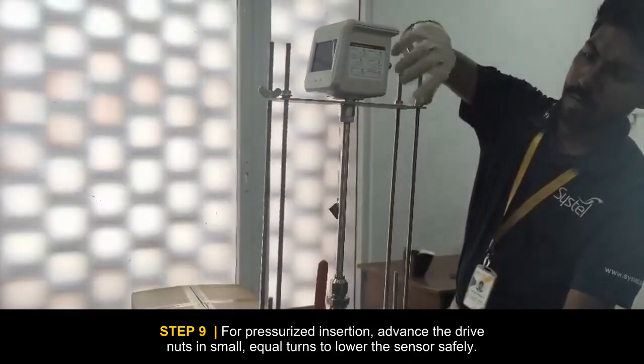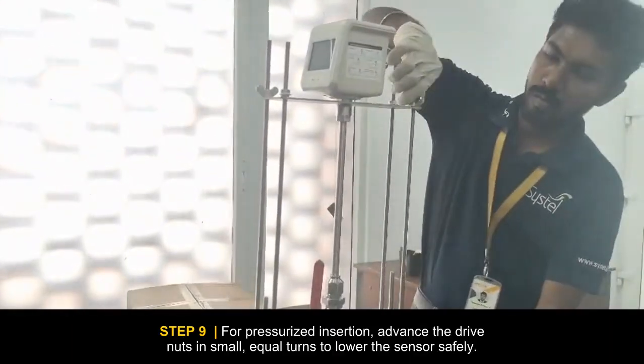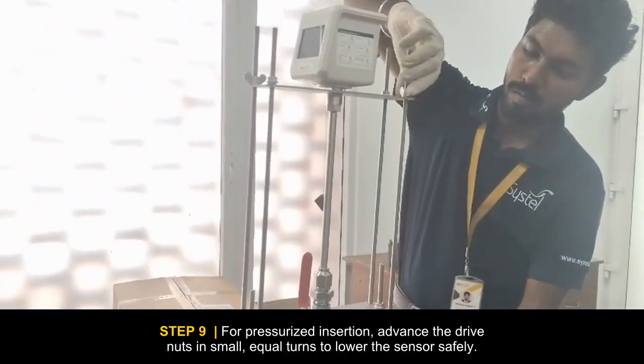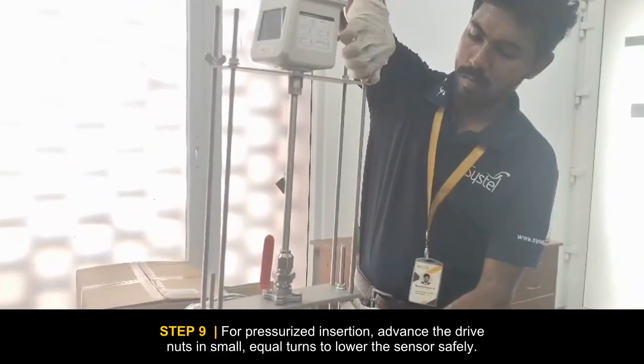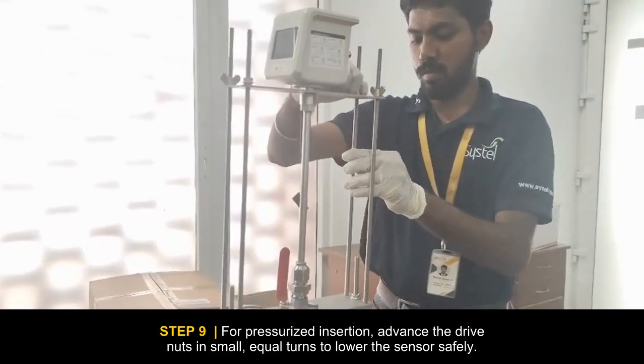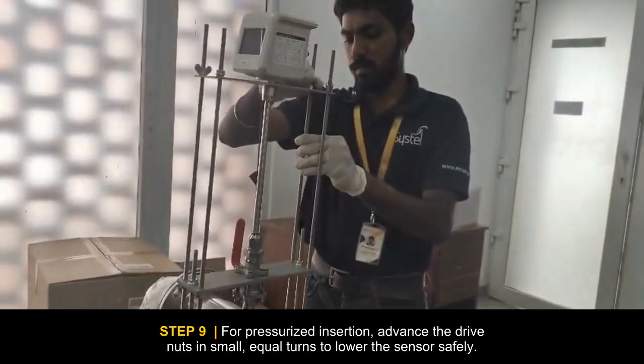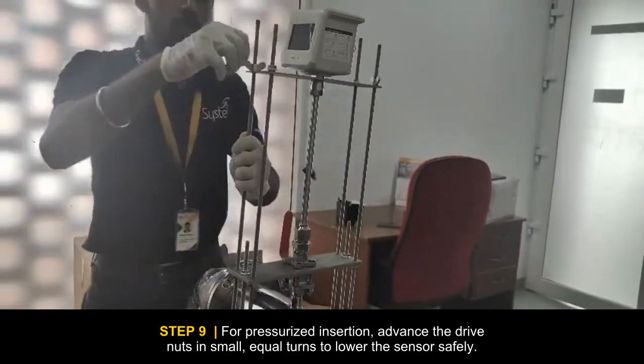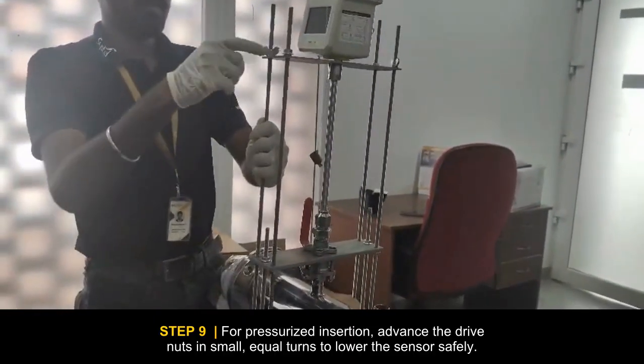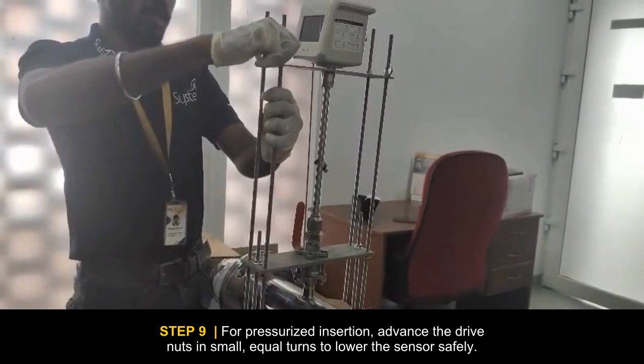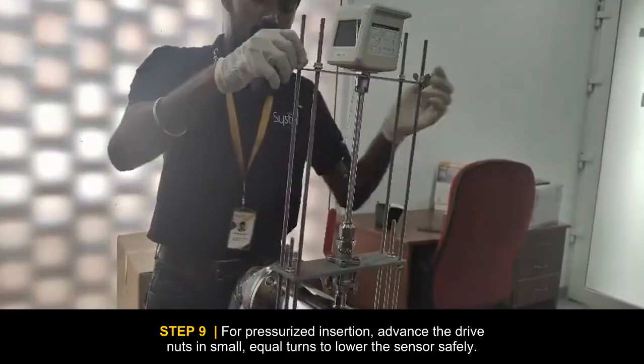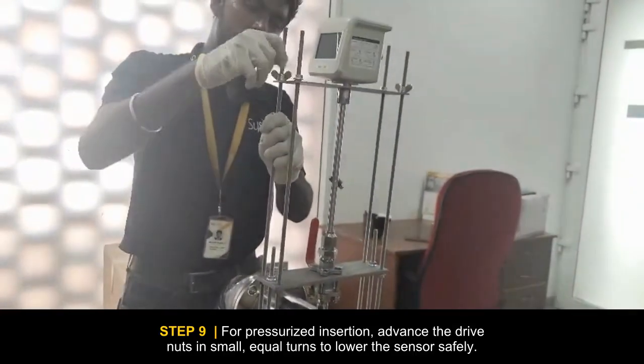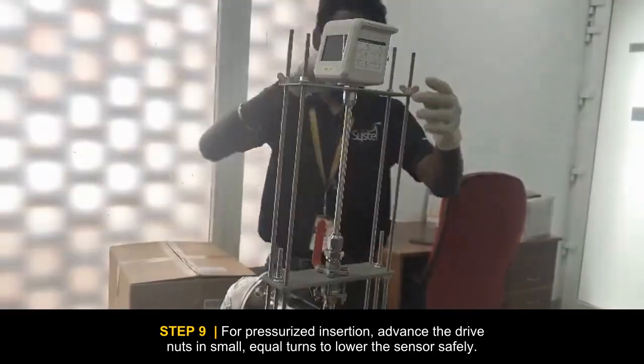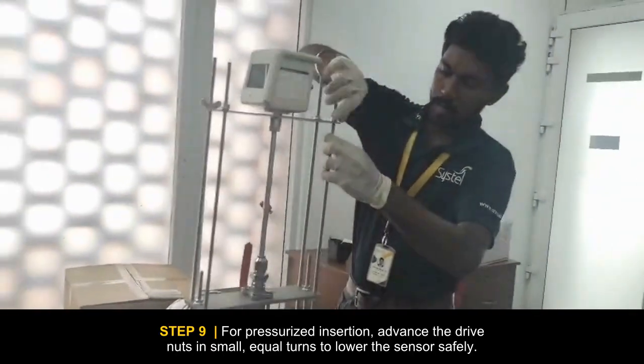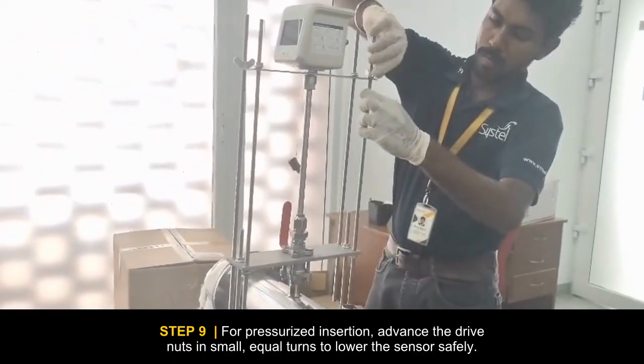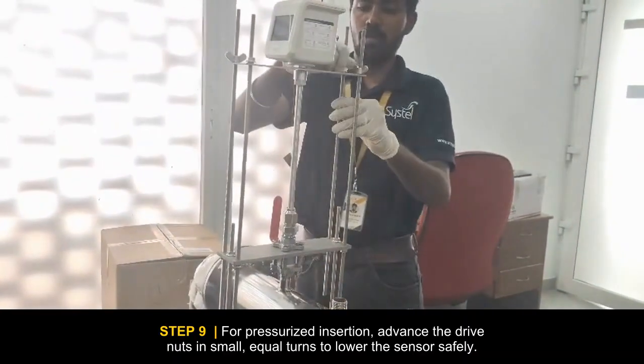Continue lowering in measured increments. Do not force the probe or allow the plate to tilt. Stop immediately if movement becomes uneven. As the sensor approaches its final position, compare both drive nuts and confirm that the upper plate remains level.